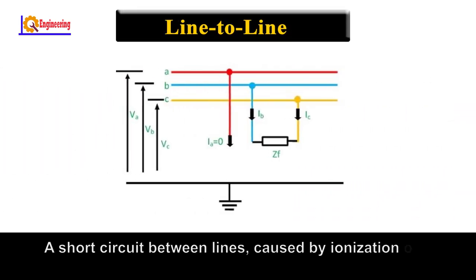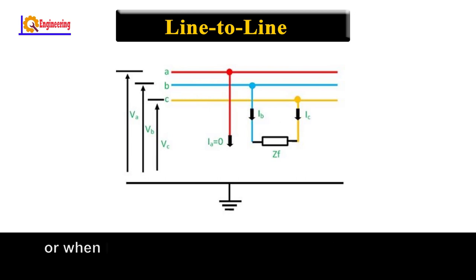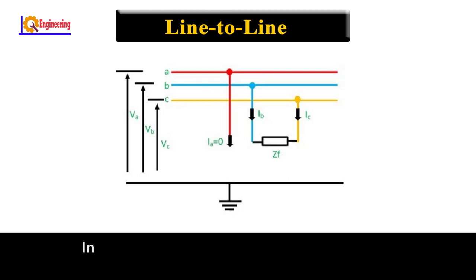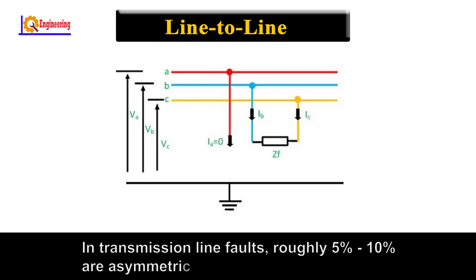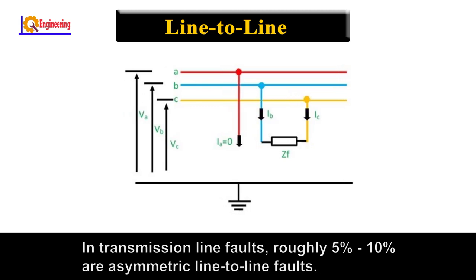Line-to-line: A short circuit between lines caused by ionization of air or when lines come into physical contact, for example, due to a broken insulator. In transmission line faults, roughly 5% to 10% are asymmetric line-to-line faults.